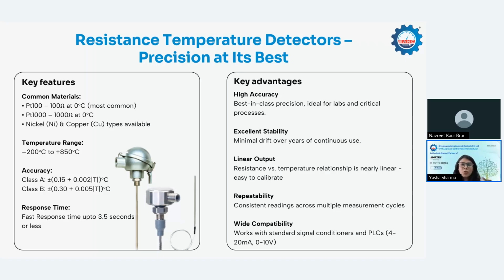The most common materials for manufacturing RTDs are PT100 and PT1000. So what is the difference between them? PT100 has 100 ohms of resistance at 0 degrees centigrade, whereas PT1000 has 1000 ohms at 0 degrees centigrade. So if you want better resolution, you should go with PT1000.